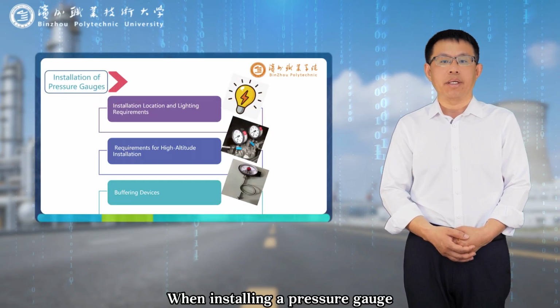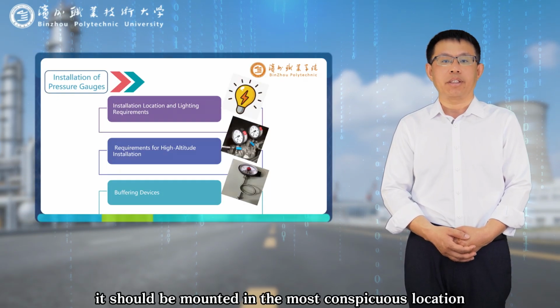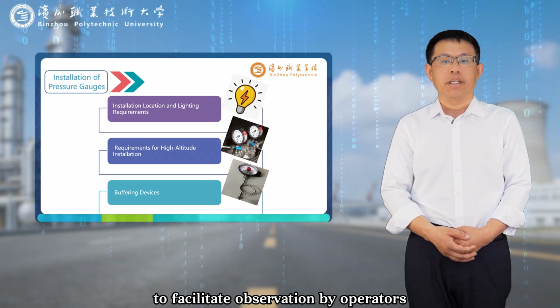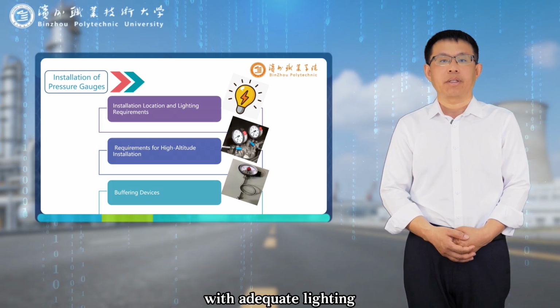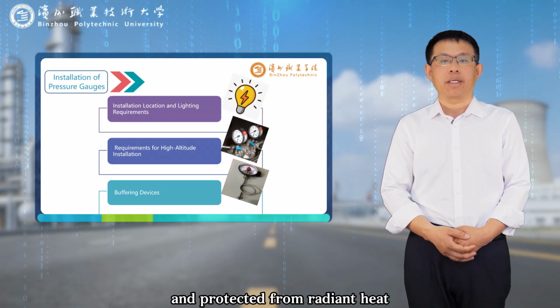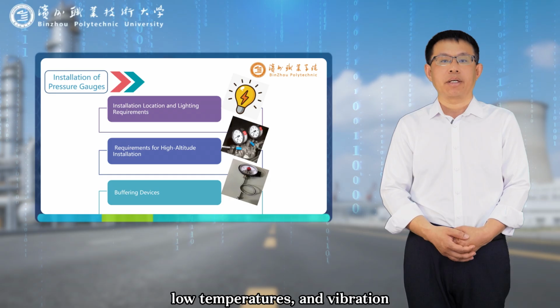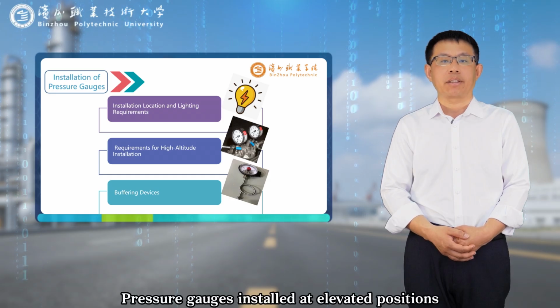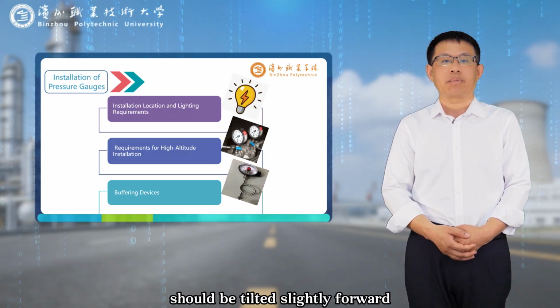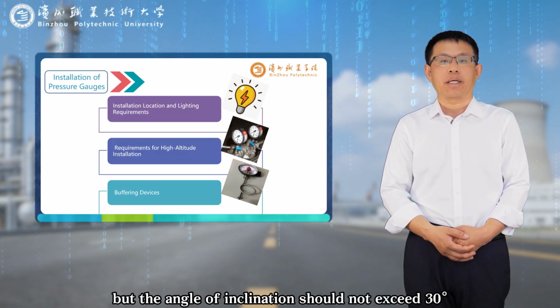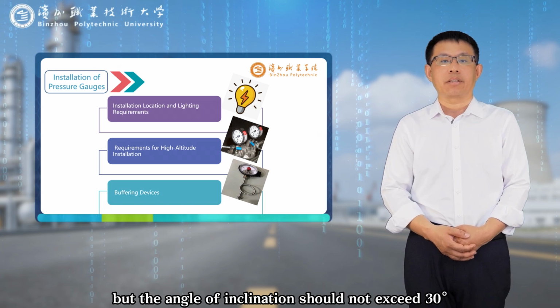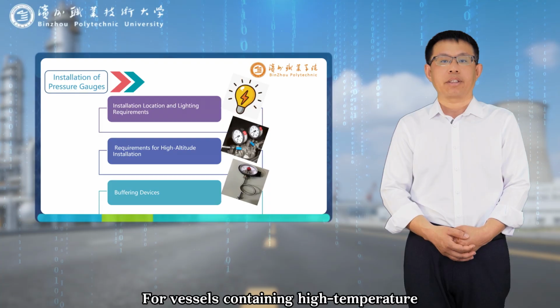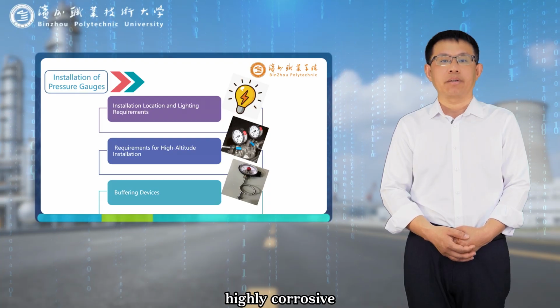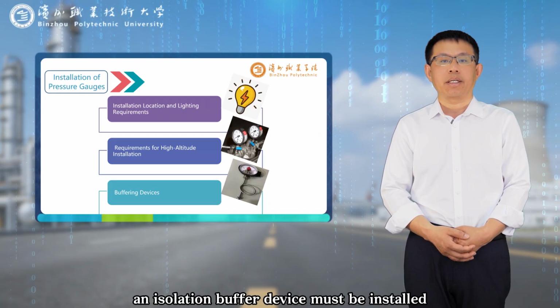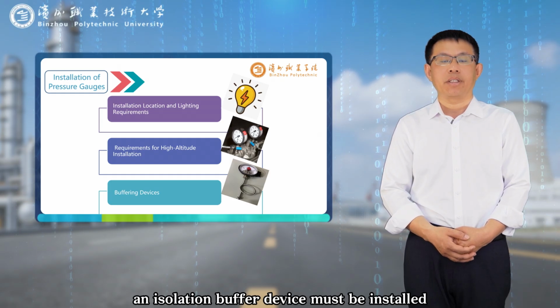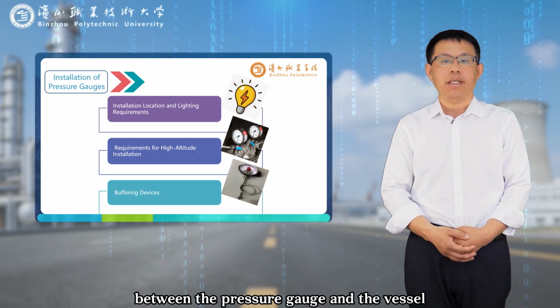When installing a pressure gauge, it should be mounted in the most conspicuous location to facilitate observation by operators, with adequate lighting and protected from radiant heat, low temperatures, and vibration. Pressure gauges installed at elevated positions should be tilted slightly forward, but the angle of inclination should not exceed 30 degrees. For vessels containing high temperature, highly corrosive, or condensable media, an isolation buffer device must be installed between the pressure gauge and the vessel.